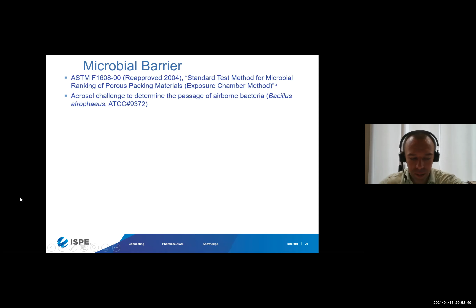On one side of the material, we challenged with approximately 10 to the 7th bacterial spores, and we collected the amount of bacteria on the other side of the material, and calculated a log reduction value. So really a filtration efficiency through the material itself. And for the polyolefin or Tyvek material, we saw over a 4 log reduction versus the paper had a 2 log reduction. So in summary here, the test results indicated that the polyolefin materials prevent passage of greater than the 4 log microorganism population, which calculates to greater than a 99.99% spore retention effectiveness.